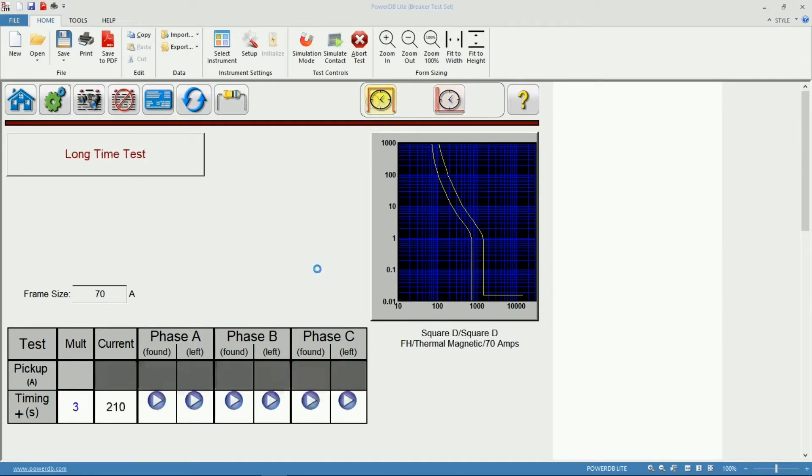Let's go ahead and start with my Long Time Test. Since we selected a circuit breaker from my library, I already have my frame size and the software calculated the current that I will need for this specific Long Time measurement.